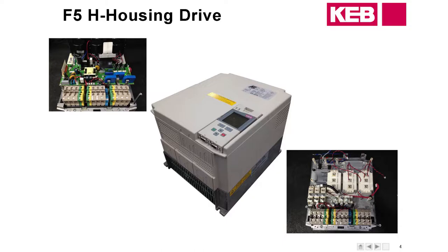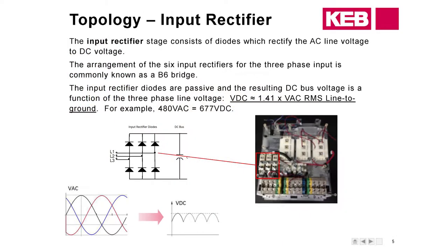Alright, so the input rectifier. If you were to take the keypad and everything off of the drives in front of you and actually look at the power stage board itself, this is what the input rectifier is going to look like. You've got one for each phase, and again this is what takes your AC sine voltage and turns it into a DC voltage.